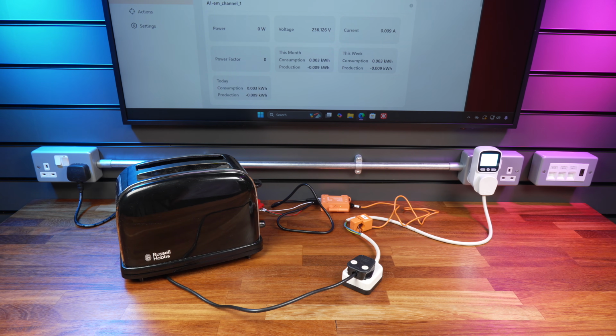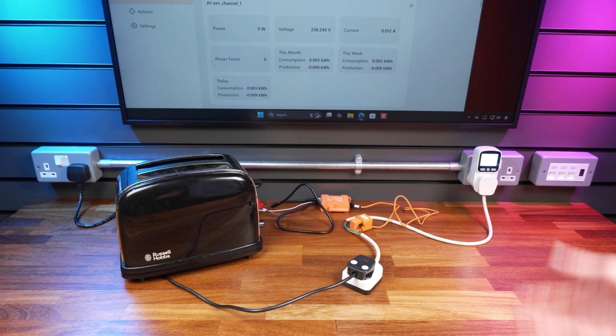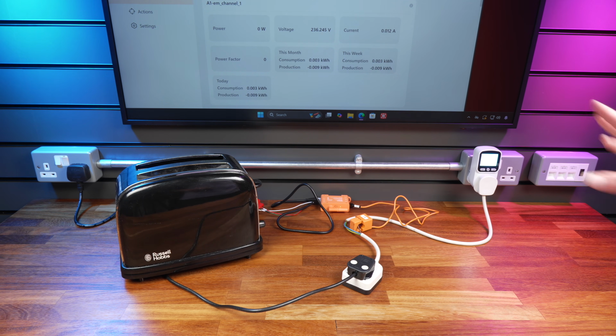So we can measure the power consumption both through the CT in the interface here, and on the plug-in power monitor, and compare the values. I don't know if the screen on this thing's showing up particularly well, so I'll read the values out in case it doesn't show up on camera, but should be good to go. So first test we're going to do is with a purely resistive load, which is this toaster.